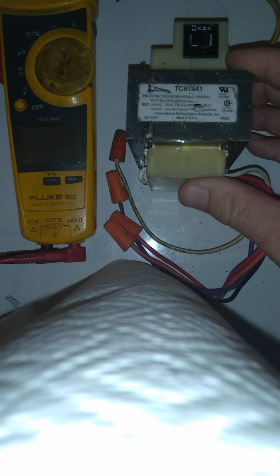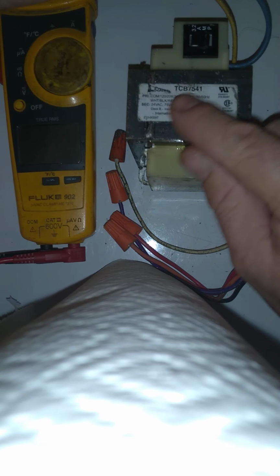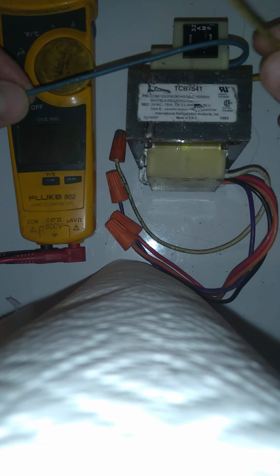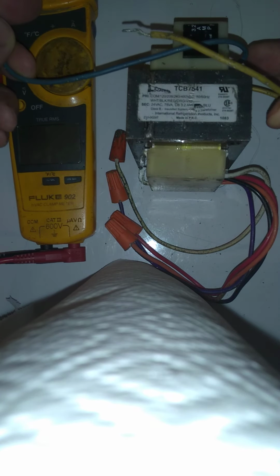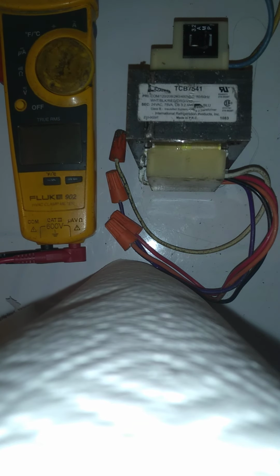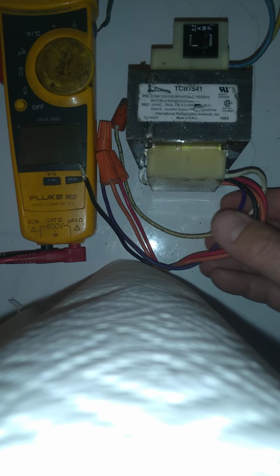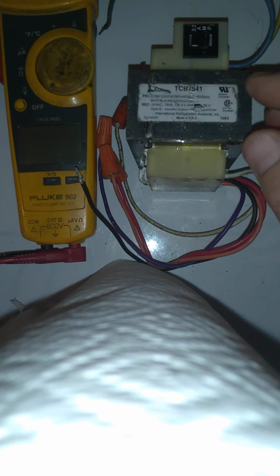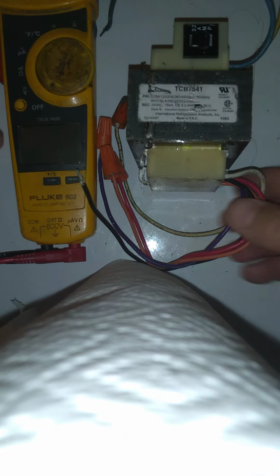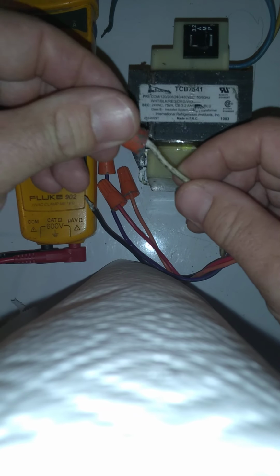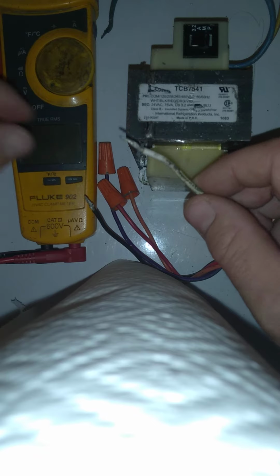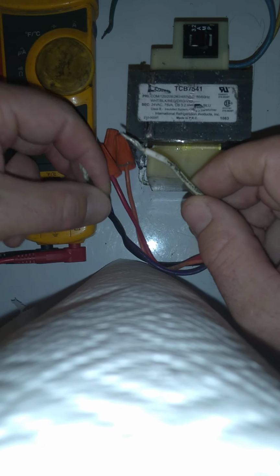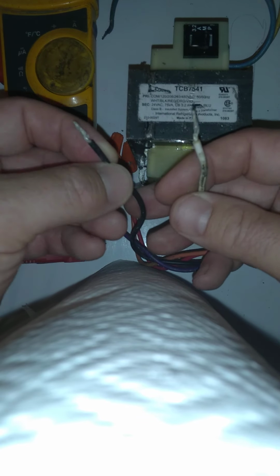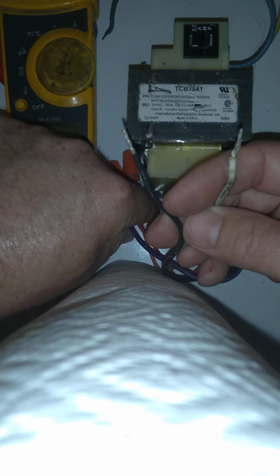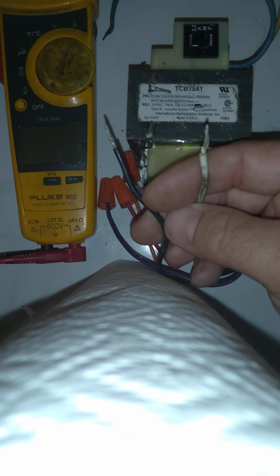Okay, in order to wire this up, I would simply take my 24 volt side, blue and yellow, and I would wire these to my 24 volt contact, my wires, my low side voltage. Okay, and then my high side, I would have to figure out which colors I needed. And let's say I had 120 volts. I would take my common, which is white. You see white, okay? I would wire this in to my common, and then my 120 is black. So I'd find my black wire, and I'd wire this into my 120 side. The rest of these, you got to put a wire nut on, or you're going to be in trouble later.